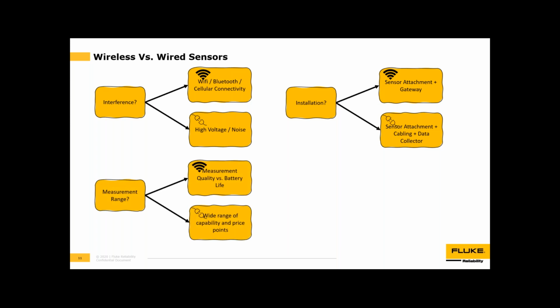Measurement range—meaning the frequency range of these sensors—is another factor. On the wireless side, there's typically a measurement quality versus battery life trade-off. If you want higher frequency data or higher quality graphs and data sets, you may lose battery life to get that. That might deter a project or not be an issue at all, depending on the asset being measured.